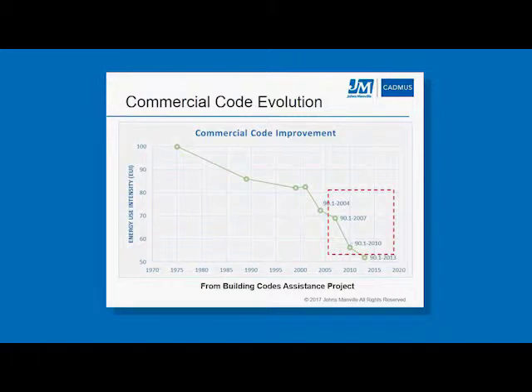Some of you may have already seen the slide about the evolution of ASHRAE 90.1 from an efficiency standpoint over the number of years. And I'm putting this up primarily because ASHRAE is referenced in the International Energy Conservation Code. So you can either use the IECC or you can use ASHRAE 90.1. As you can see, from ASHRAE 90.1 2004 down to 90.1 2013, which is the last published, there's been a significant increase in efficiencies. Between the 2004 and the 2007, there was roughly a 5% increase in efficiency, and between the 2007 and 2010, we were looking at roughly a 25 to 28% increase in efficiency.